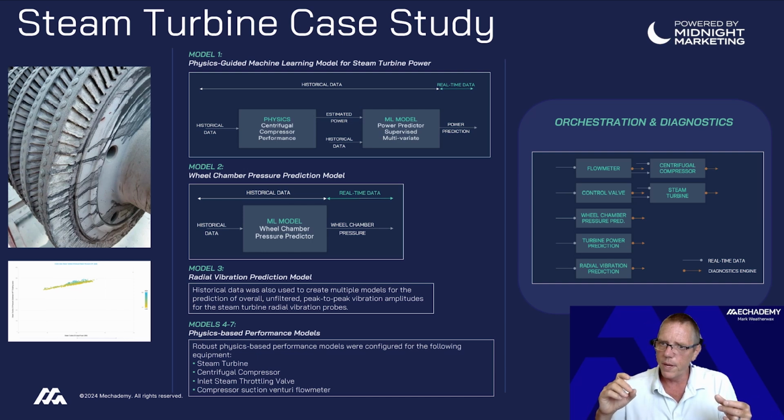And so being able to understand what the compressor's power was, was a big factor on having to understand the mole weight, right? So you needed both sides of this. When it was clear it was running on hydrogen and you knew the power, you could use that data and train a machine learning model to understand this condensing steam turbine. You come in with a pressure and temperature of steam, you expand across the turbine, and you come out in the two-phase region, somewhere between 100% steam and 100% water. And so you're at some quality level in there, right, of steam quality.